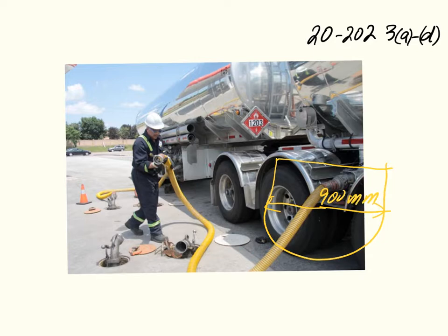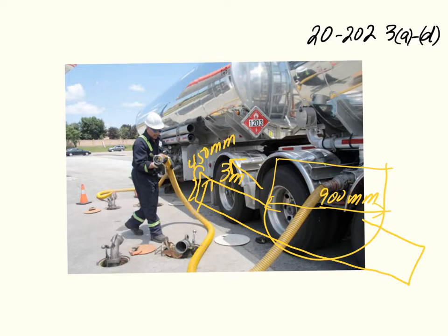Now, one other part to consider is the area down where this gentleman is standing in the picture. So essentially from that outlet point, there's also an area that extends like this, and that goes out 3 meters and comes up 450 mil from the ground.